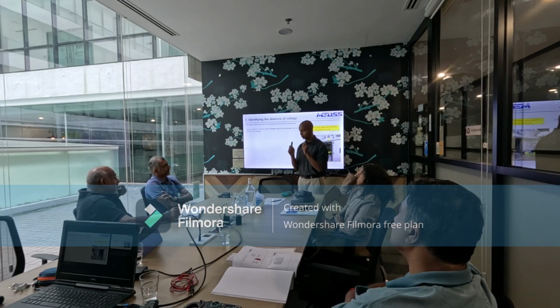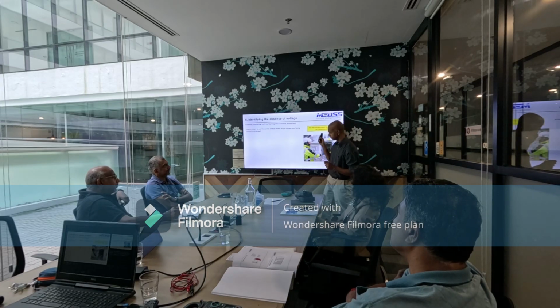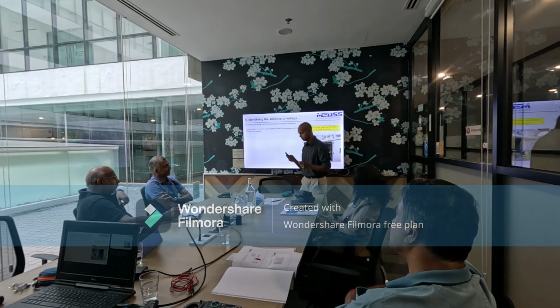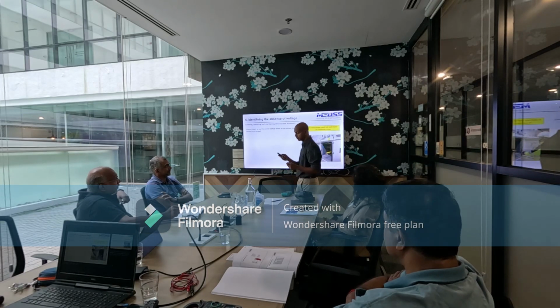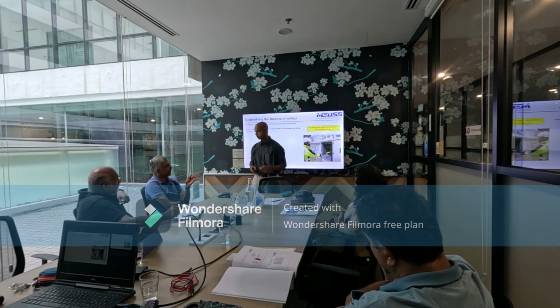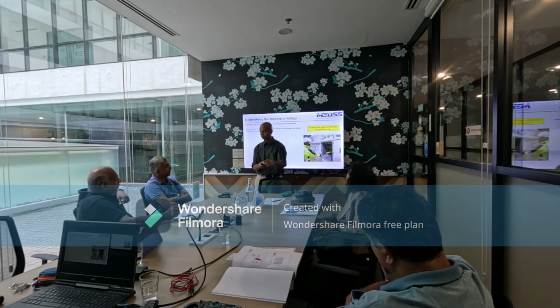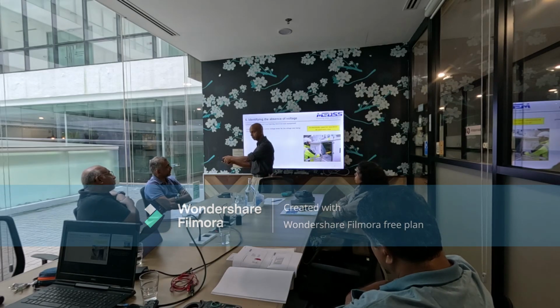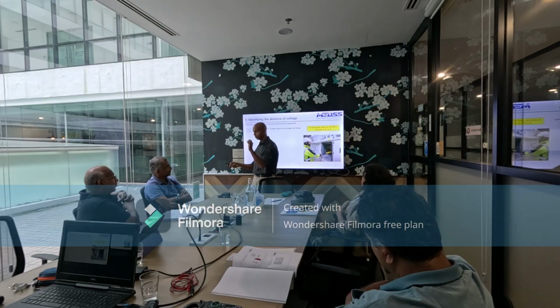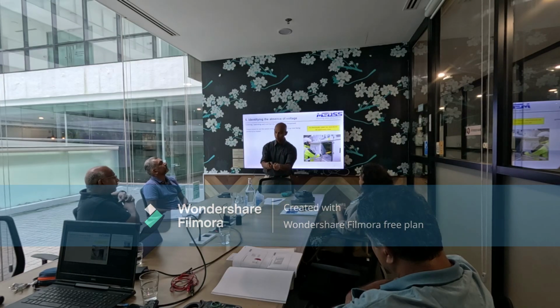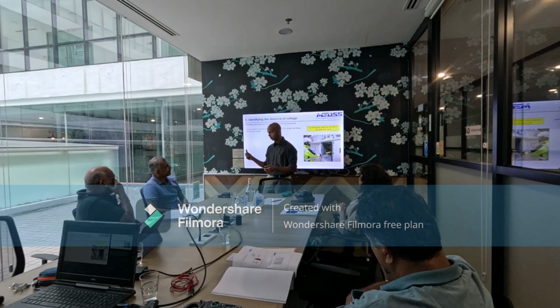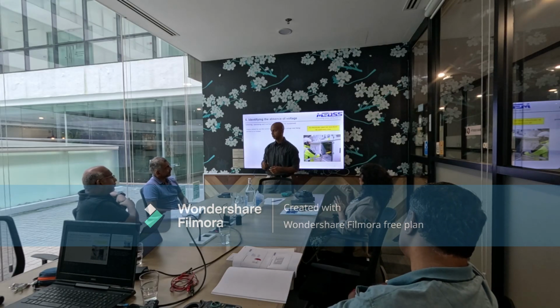Before you start work, you have your voltage tester. Whether it's LV or MV, it doesn't matter. Before you test, you have to check it on a known source, meaning it's live. You check it's working, then you test the part where you want it to be zero voltage, zero energy. Once done, you go back to the known live source and test again. That ensures your voltage tester is in working condition.